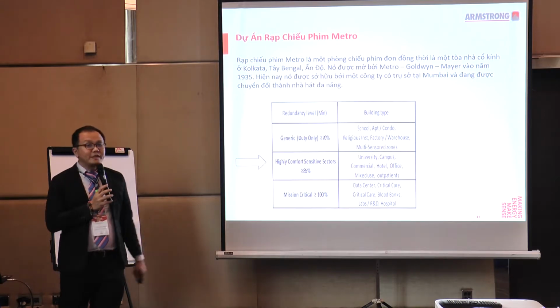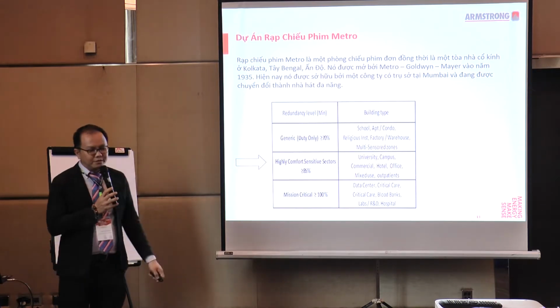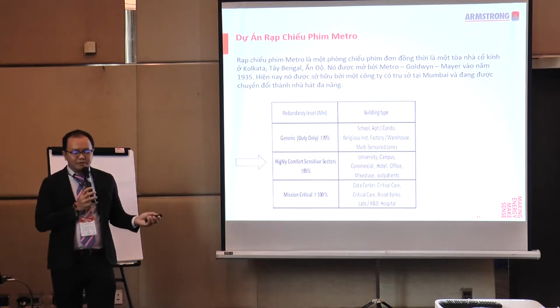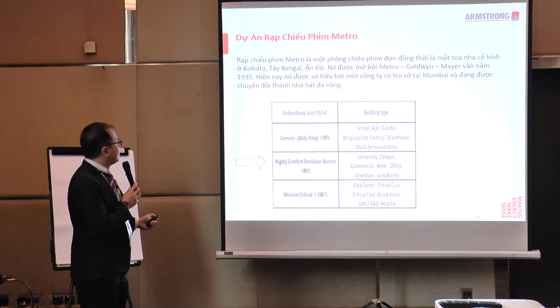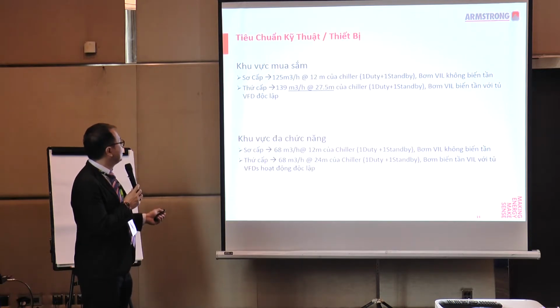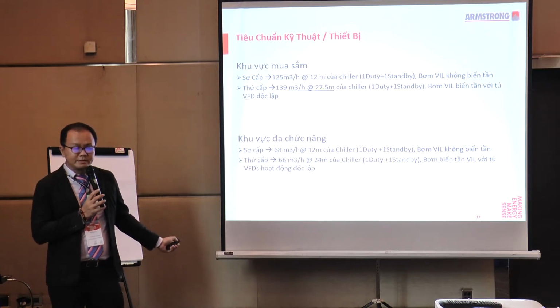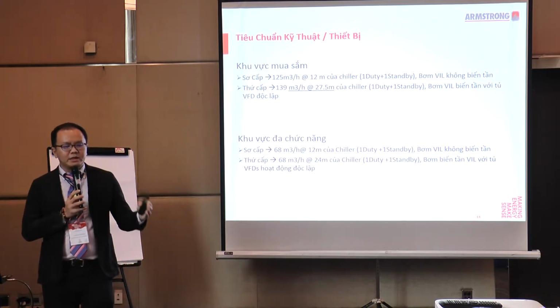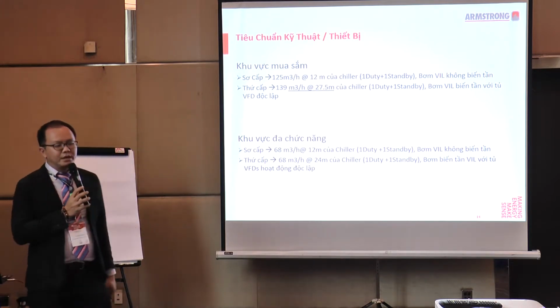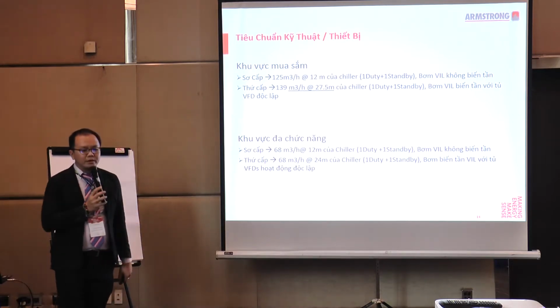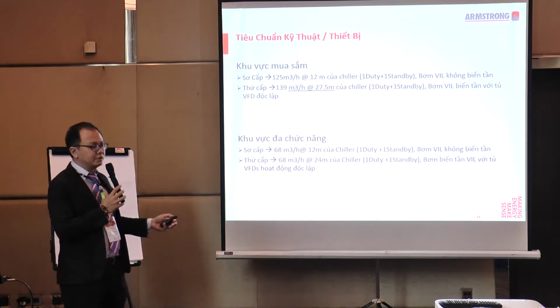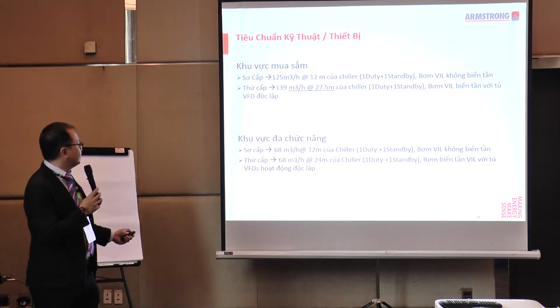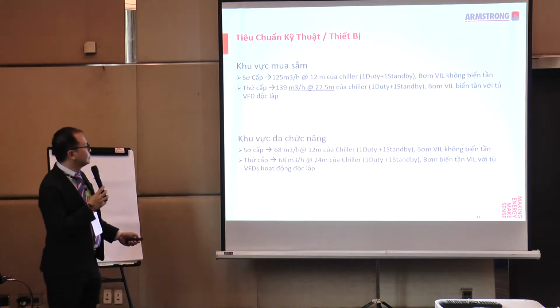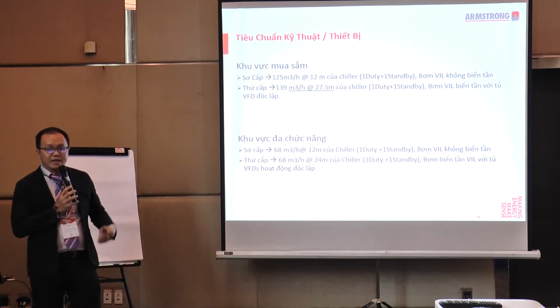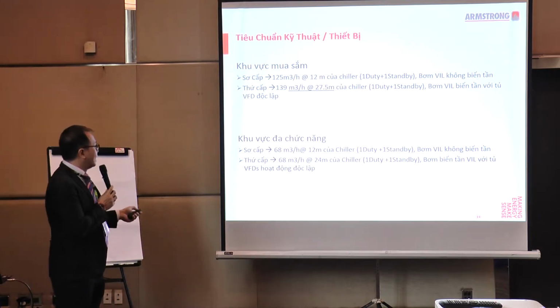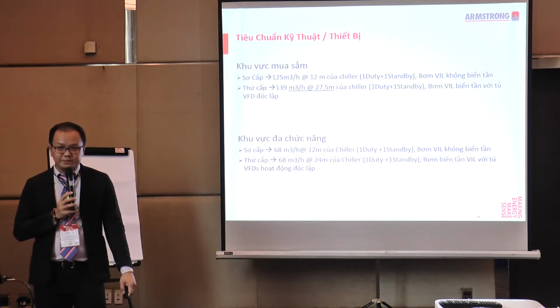So back to this cinema here. This is essentially what the customer is looking for, a 1930s up to 60s type of design. It comprises two parts: the mall area and the multiplex. For the mall area, we have a primary running with constant speed, and the secondary running with an attached VFD at this requirement. For the multiplex, you have the constant speed and also the pump with an attached VFD as well. One has a higher requirement, and one a slightly lower requirement.